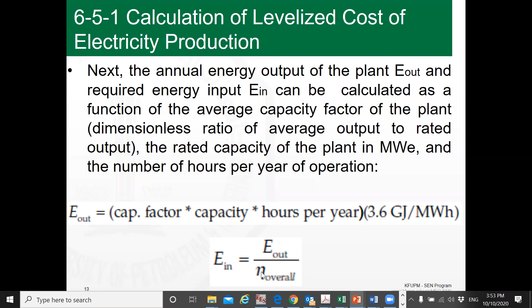Now, the efficiency of the boiler, I mean the combustion here, is 85%. This is eta combustion. And eta generator is 98%. So we can multiply 85 times 98 times the efficiency of the plant, which is 80% of the efficiency in example 6.1, and get the overall efficiency. The plant is rated at 500 megawatts. This is a simple Rankine cycle, 500 megawatts, and it has a capacity factor of 70%. You remember, this is the equation we are using to get output power. Capacity factor 0.7, capacity 500 megawatts, number of hours in a year, 8,760. So we have all these numbers: 0.7 times 500 megawatts times 8,760. This gives you megawatt hours, multiplied by 3.6 gigajoules per megawatt hour. So whatever the number, it will be in gigajoules. And we divide this by eta overall, and it will give us the energy in, right?